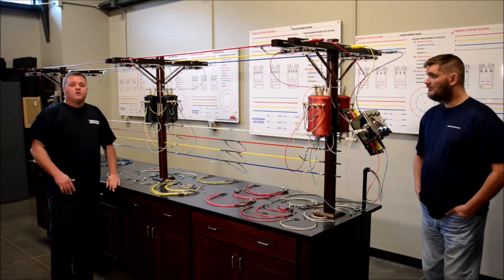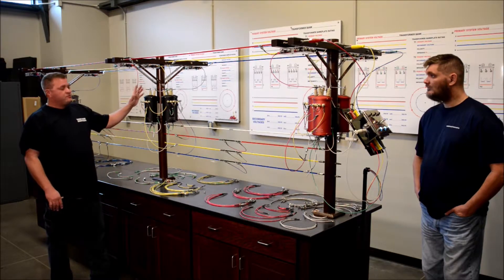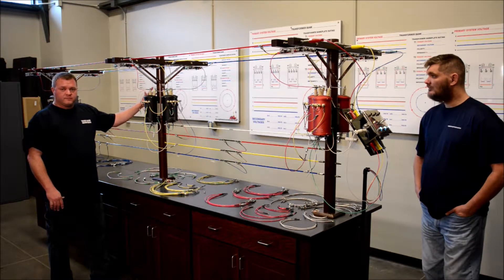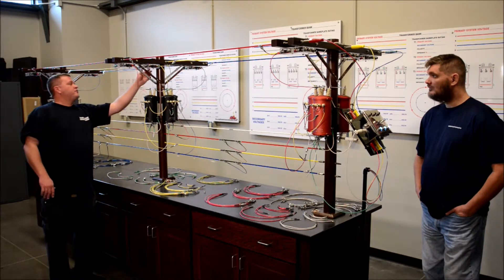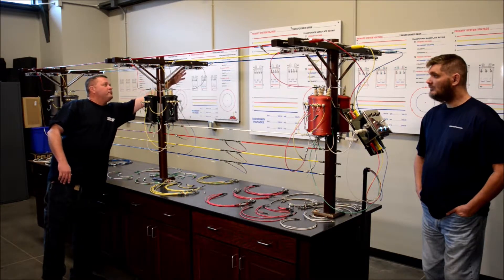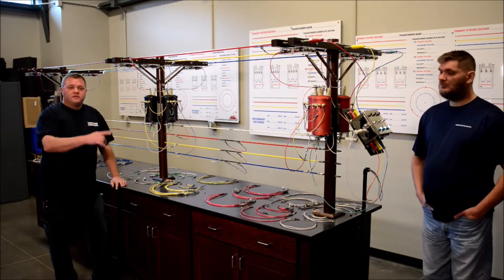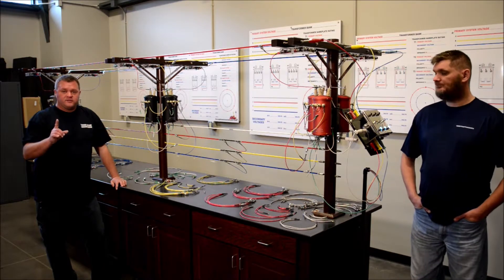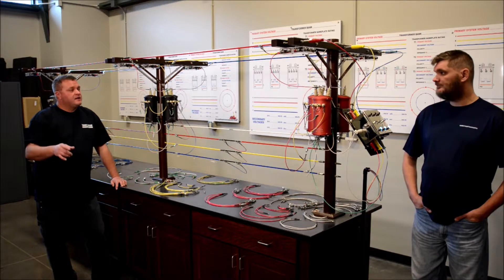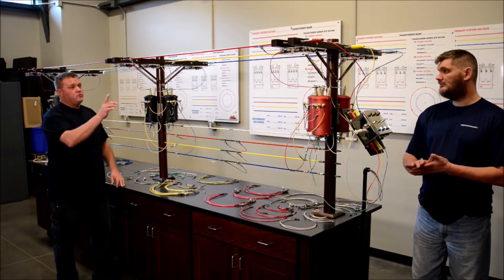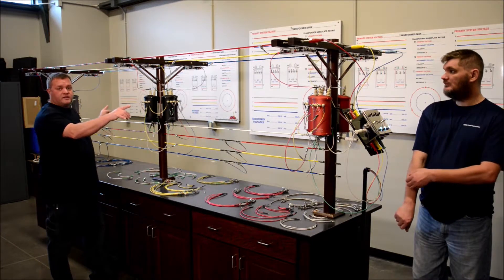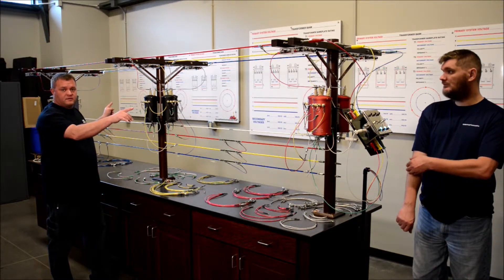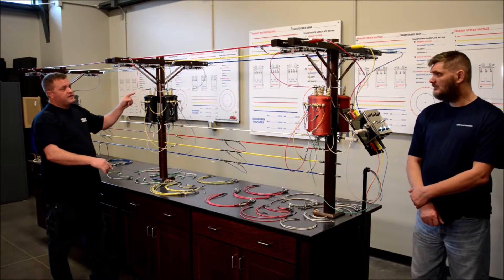So in this demonstration, what we're going to do is I have got this bank completely built, ready to go. All the cut outs are closed, or the breakers. Jason is going to energize one phase on this primary system. And I want you to watch every one of the lights come on the system. Now on the other two banks, the green lights are going to come on. Those banks are not closed, just this bank.